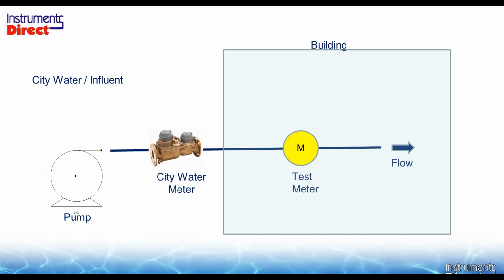It's a matter of relevance and a matter of flow rates. Did you know that a flush of water with an old-fashioned toilet is about 1.5 gallons? New stuff, less than that. So 1.5 gallons in an 8-inch carbon steel pipe equals 0.0767 feet per second. I am not aware of any ultrasonic meter, for that matter any magnetic flow meter, any turbine flow meter, that can read that low. So you're going to miss toilet flushes on a large line size like that. When the flow rate gets higher, you're doing good. So in that case, if you're going to monitor this, you need to have the right equipment.